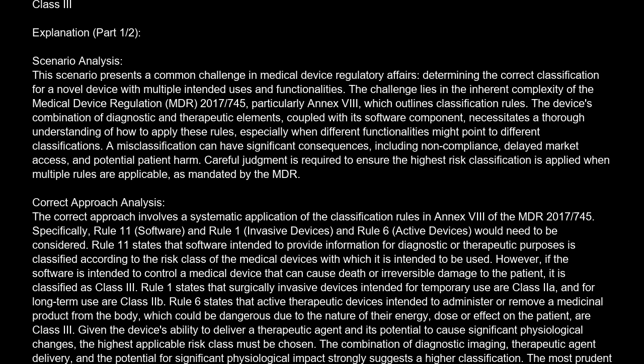Rule 11 states that software intended to provide information for diagnostic or therapeutic purposes is classified according to the risk class of the medical devices with which it is intended to be used. However, if the software is intended to control a medical device that can cause death or irreversible damage to the patient, it is classified as Class III.